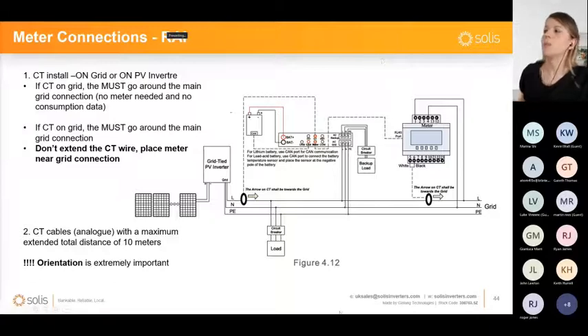So when the inverter comes, it's delivered with the meter itself, but it also comes with a CT clamp. You can either choose to have the CT clamp as it was before, CT installed on grid, or if you are installing the meter as well, then you have the option for CT installed on PV inverter. What does this mean? When the CT is installed on the PV inverter, it should be installed on the output of the grid-tied inverter, so it can constantly know what the system is generating. Based on this value and what the meter is measuring as export to the grid, that difference would mean the consumption value for the customer.